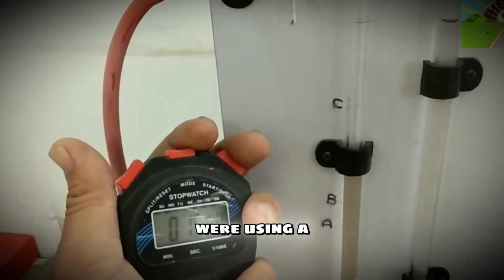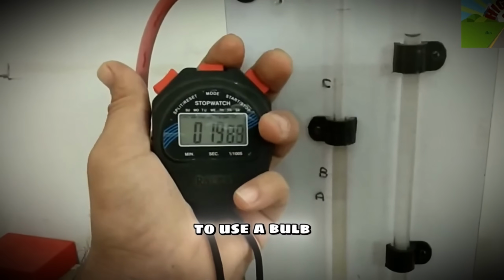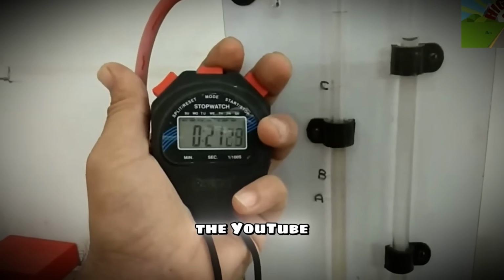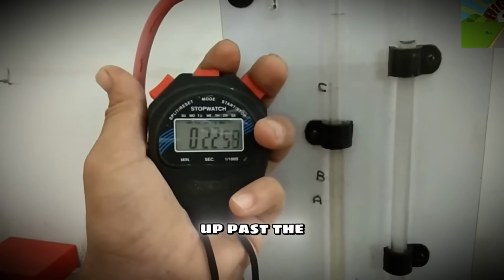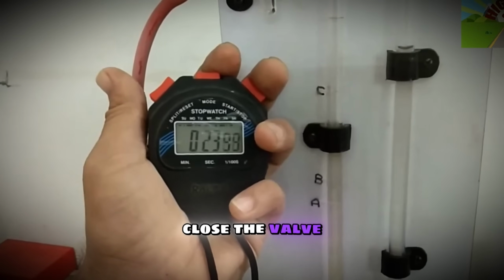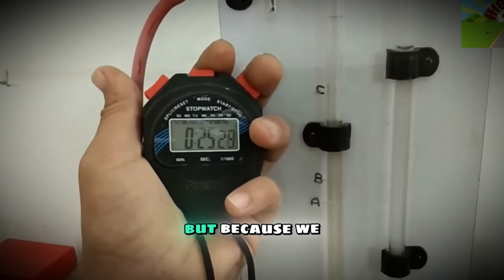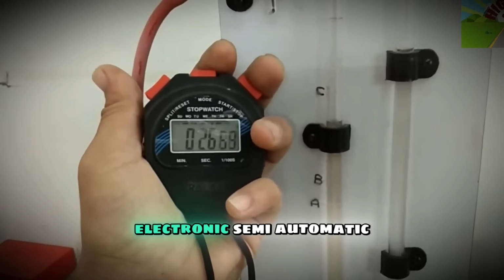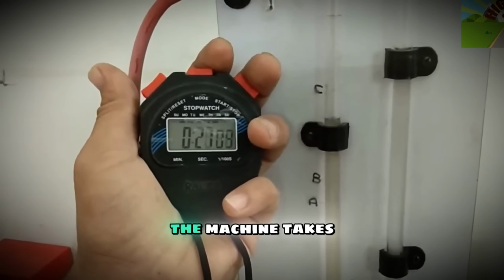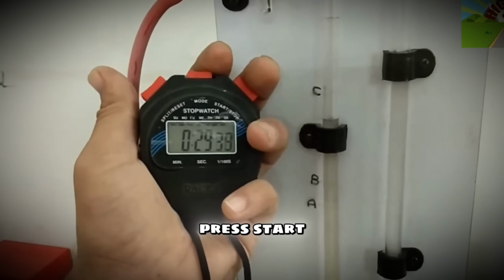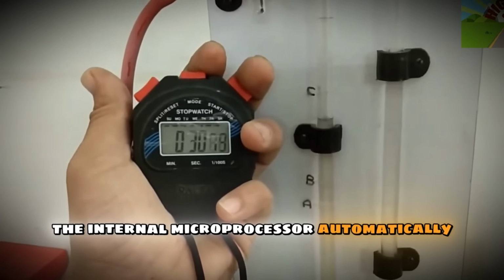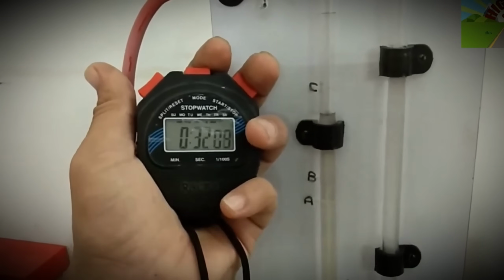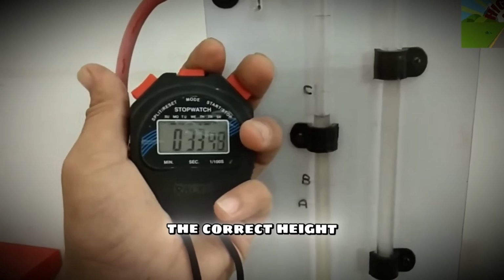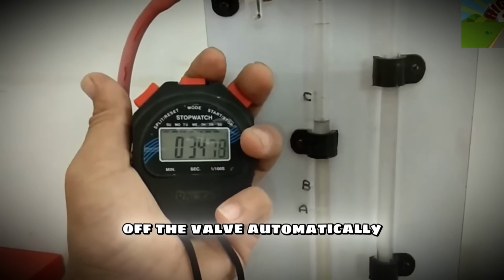Now, if we were using a manual apparatus, I would have to use a bulb to suck the air out of one side of the U-tube, drawing the fluid up past the top timing mark, close the valve, and sit with my stopwatch. But because we are using the Blaine apparatus, electronic, semi-automatic, the machine takes over. I simply press start. The internal microprocessor automatically activates a small pump, drawing the manometer fluid up to the correct height. It then shuts off the valve automatically.